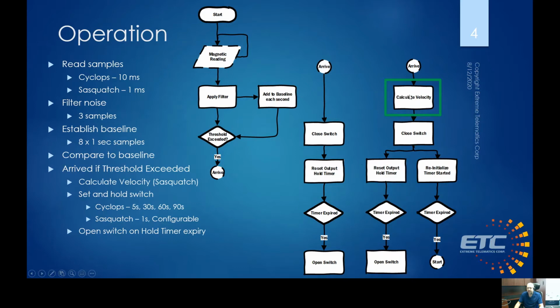Now, things are a little bit different for the Sasquatch. There's a couple other states that are injected in here. Before we actually close the switch, we calculate the velocity. And the reason we do this is when we go and close the switch, which goes to your RTU or PLC or your plunger controller, we want to make sure that the velocity is in the Modbus register and ready. So we first calculate the velocity based on the data we've been gathering, then we'll close the switch.